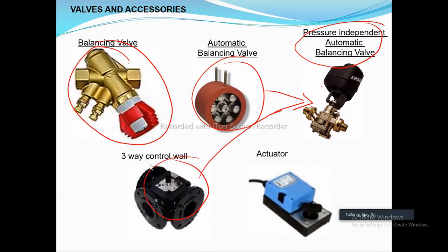If it's a three-way valve, it will allow only that much water that is required for cooling. The rest of the water will get bypassed. If it is a two-way valve, it will slowly start closing and there will be an increase in pressure. That increase in pressure will be sensed by your VFD and it will reduce your RPM accordingly. I hope it is clear. Yes, sir.